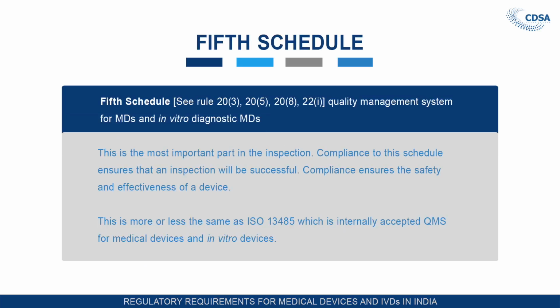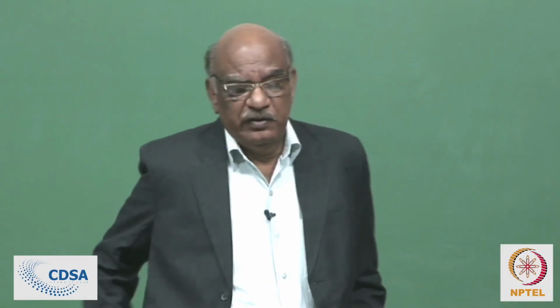Fifth Schedule, rules 20(3), 20(5), 20(8), 22(i). Quality management system for medical devices and in vitro diagnostic medical devices. This is the most important portion in the regulations, which guides the inspectors and also the applicant to set up their plant according to the norms. It is the most important part in the inspection; compliance to this schedule ensures that an inspection will be successful. Compliance ensures the safety and effectiveness of a device. This is more or less the same as ISO 13485, which is the internationally accepted QMS for medical devices and in vitro devices. So you have to follow 13485 completely, which is the QMS as mentioned in the Medical Device Rules 2017.